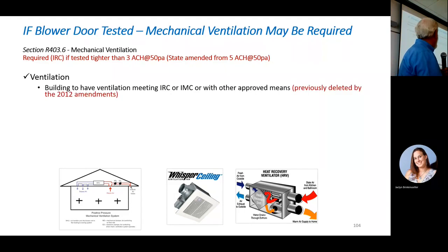Or you can do the best one, but it's by far the most expensive, and that's a heat or energy recovery ventilator. Anybody ever put one of those in? I'm sure some of you have seen them. They're an exhaust fan and a supply fan in one. So you exhaust air out of your house, run it through a heat exchanger to outside. At the same time, you bring in fresh air that goes through the other passages in the heat exchanger, grabs the heat out of the air you're throwing away to heat or preheat that cold air you're bringing in from outside. And they run 70 to 80% efficient. So they recover quite a bit of that heat. You spent money to heat it up. We're throwing it away so we can grab some of that.